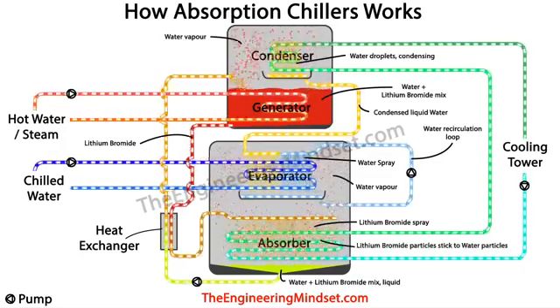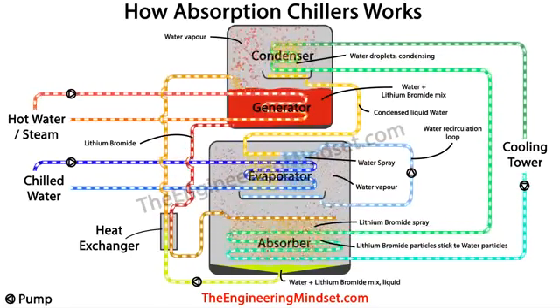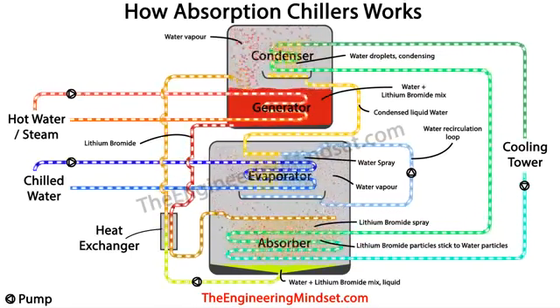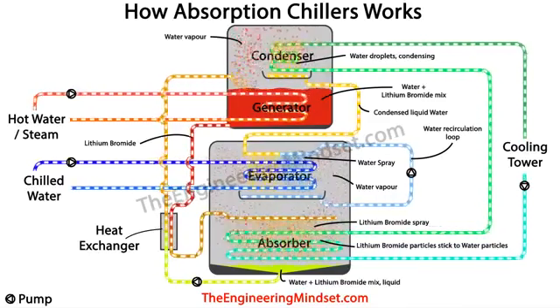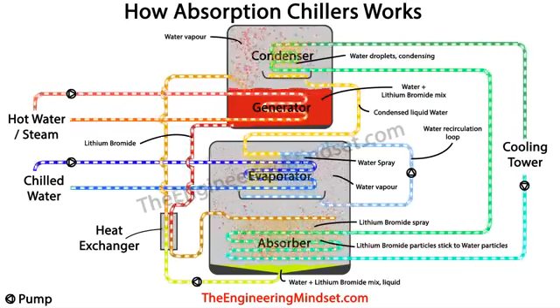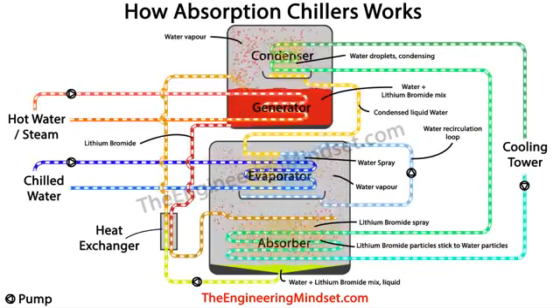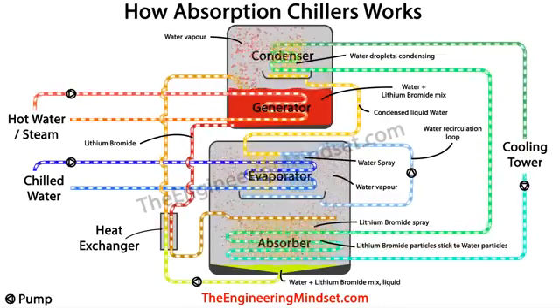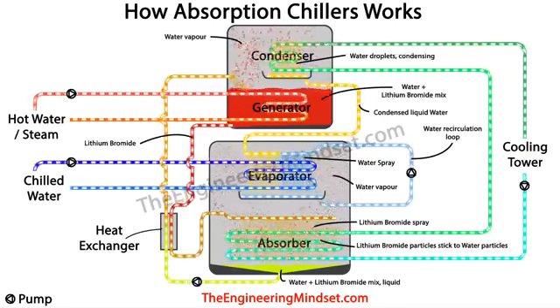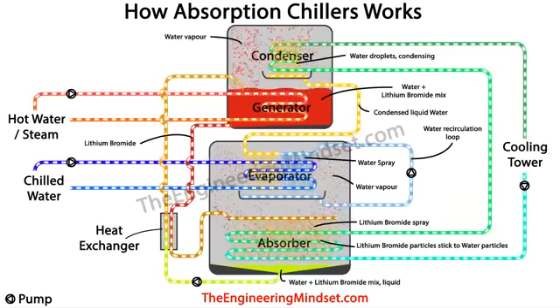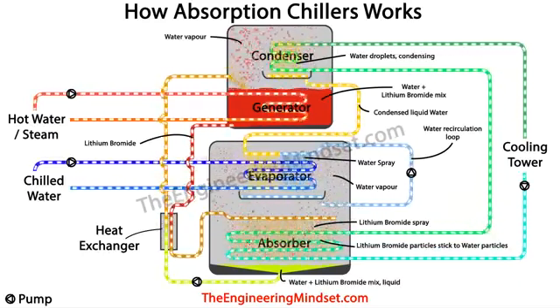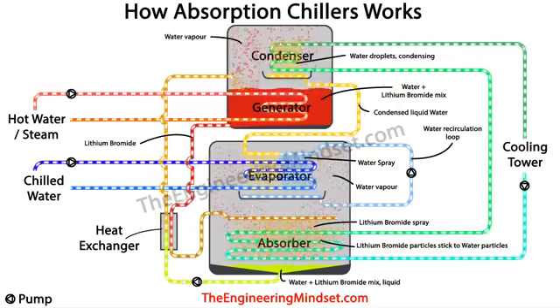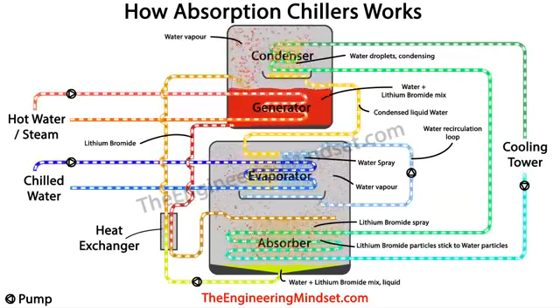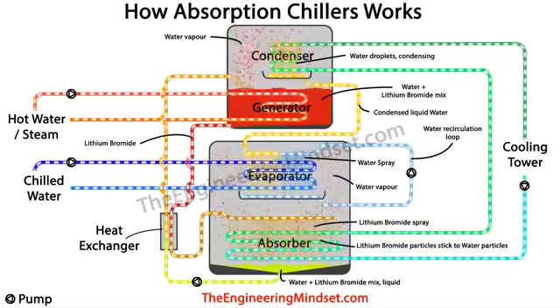Now all of this water that's evaporating into water vapor and steam will build up and collect around the evaporator chamber. And this water vapor or steam is then attracted and pulled towards the strong lithium bromide solution being sprayed in the absorber, almost like a magnetic force. The attraction is so strong that water particles flow by themselves straight to the absorber to be together with the lithium bromide particles. This strong, almost magnetic attraction between the water particles and the lithium bromide particles is what causes the vacuum in the chamber.